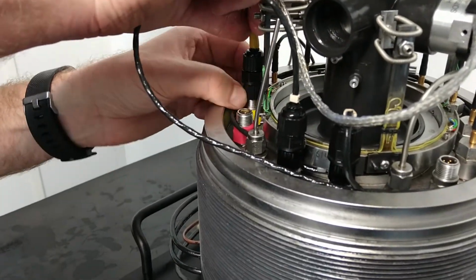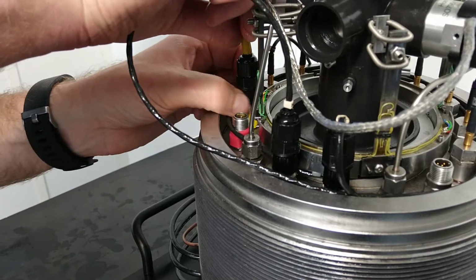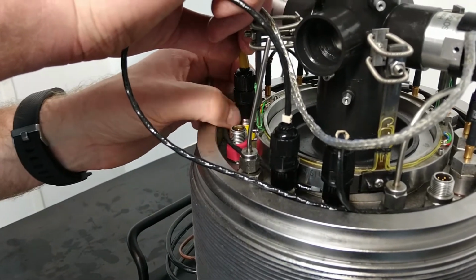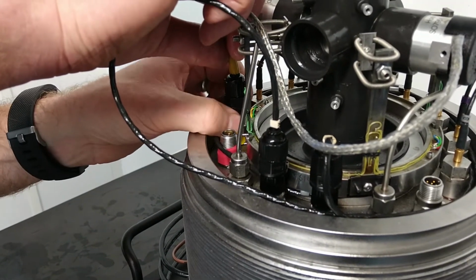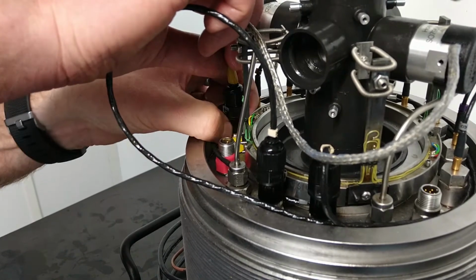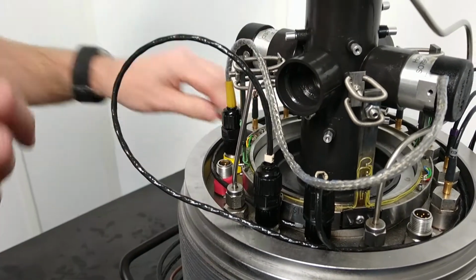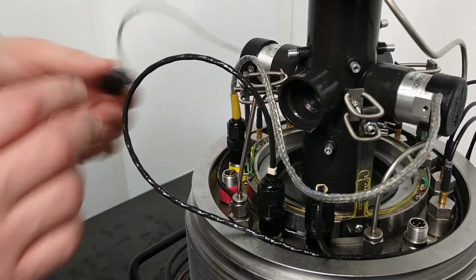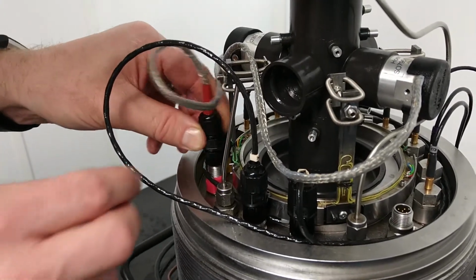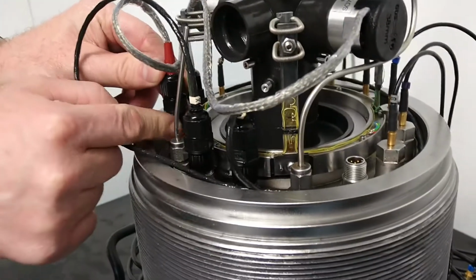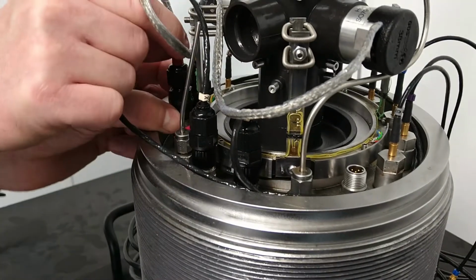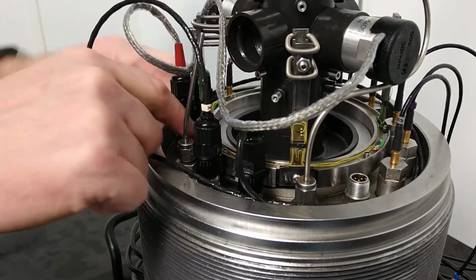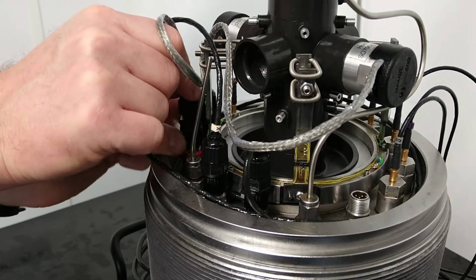When tightening the plug, only rotate the collar on the lower section. You may need to gently push down the fitting after a few rotations for this to locate fully at the bottom of the feed-through connector. Once fully tightened, it's advisable to loosen the collar by 1/4 of a turn, as specific testing conditions can cause the plug to become difficult to remove when required.